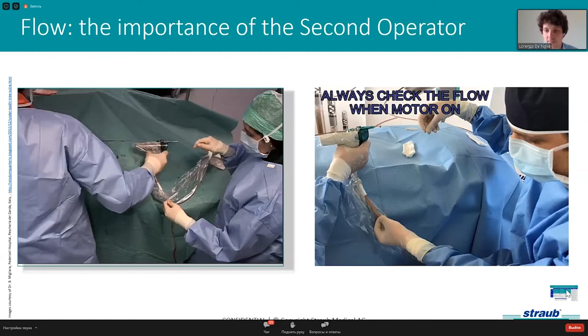We know, do not activate the motor in dry condition without the guide wire. Again, the risk of breaking, especially the big catheters, is really, really high. So flush the catheter with saline, put the guide wire on for all the length, and then again in the bowl of saline. And always start the motor in the open proximal vessel to avoid compromising the aspiration.